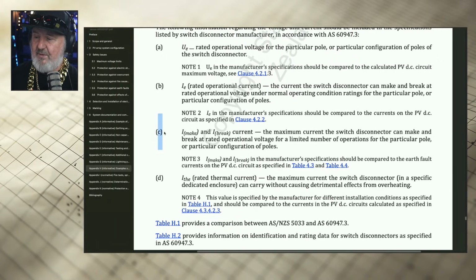So we've got, it's known as a utilisation category. I just forgot the term for a minute then. And so we require a utilisation category of DC 21B, which is at least once every 30 seconds. Now, what's a bit scary is I've looked up some products to see what the utilisation category was and what the number of operations. They only tested them for 5 operations. So to pass this test, I make and I break, you only have to do it 5 times.